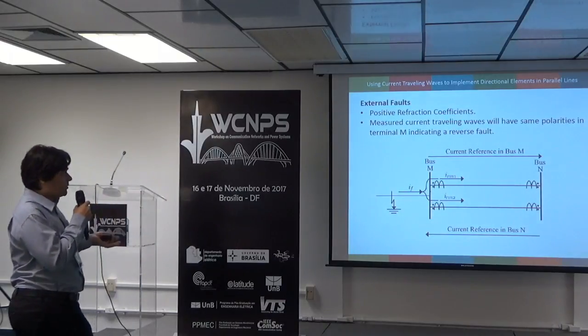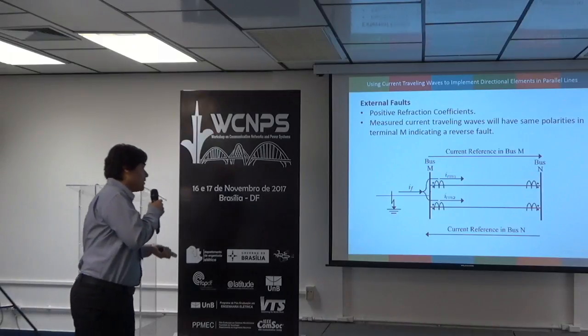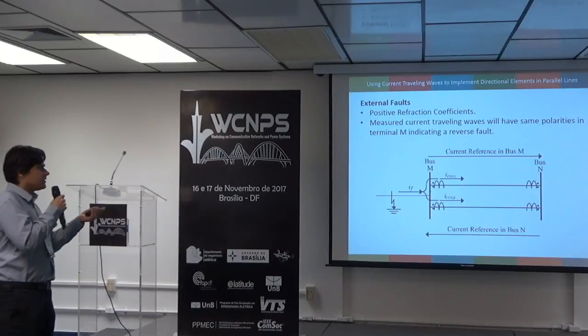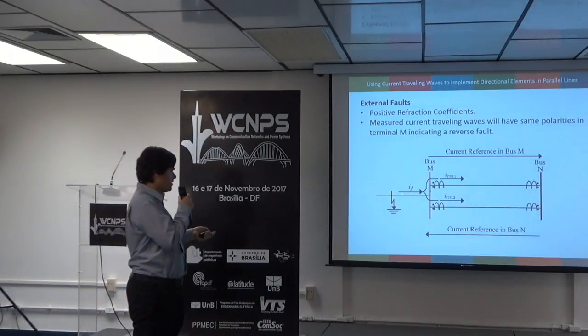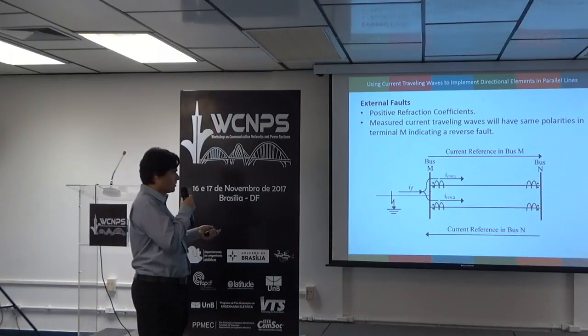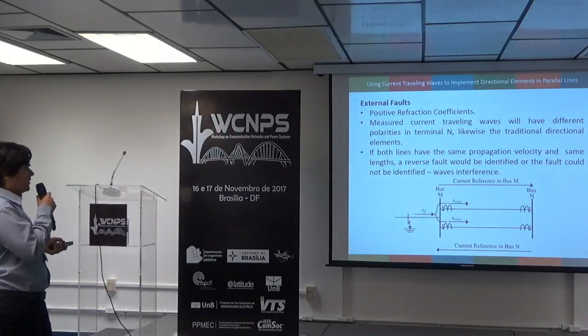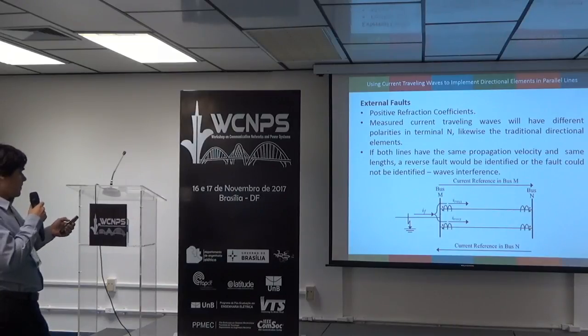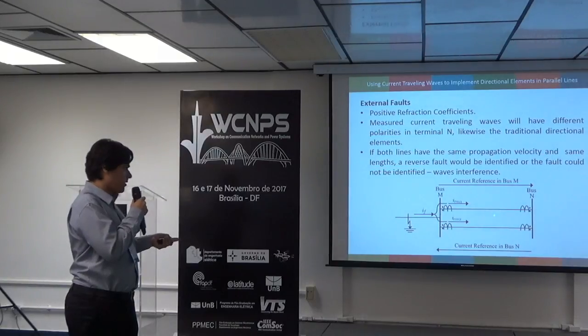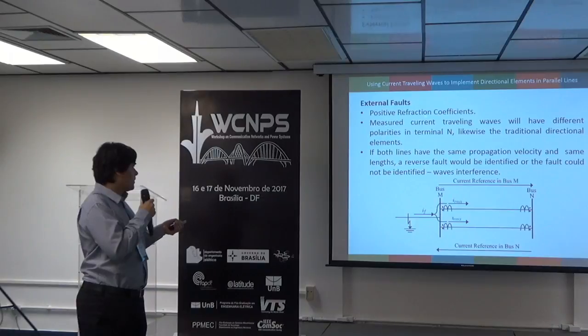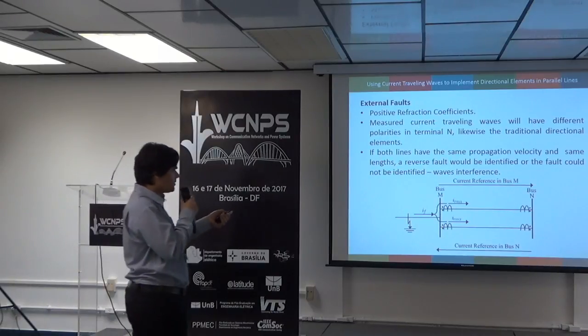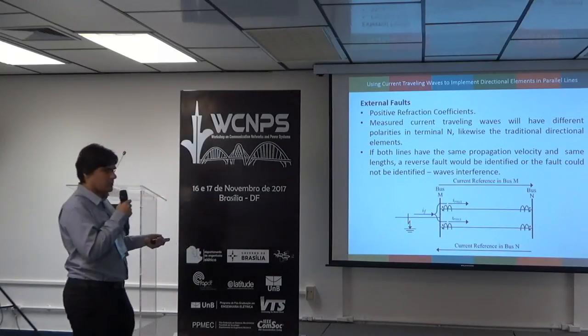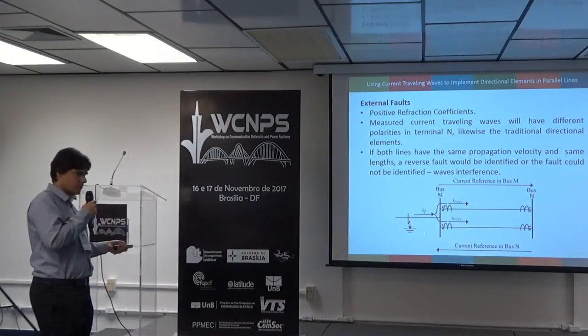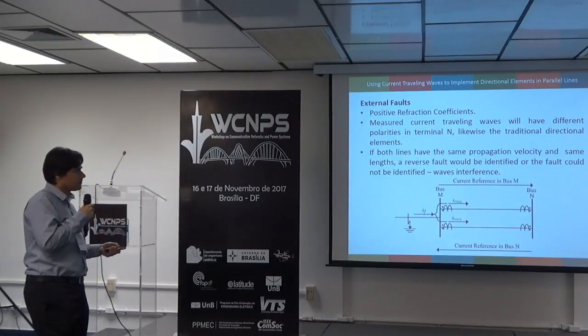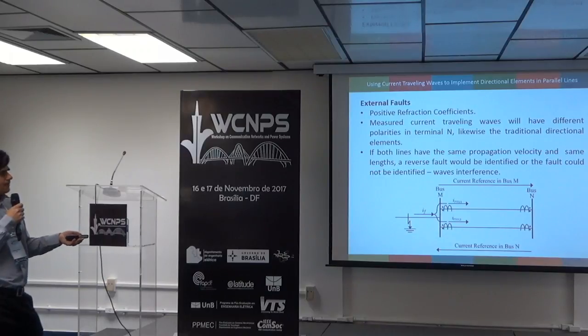External faults. Again, if you have positive refraction coefficients, the measured current traveling waves will have the same polarities in terminal M, indicating a reverse fault. This happens because the wave arrives at the bus and the refraction is seen at both current transformers of the parallel lines. But in bus N, if the waves do not arrive at the same time, the measured current traveling waves will have different polarities in terminal N, like traditional directional elements. Because in this case of an external fault, for bus M it will be a reverse fault. For bus N, it will be a forward fault. The traditional directional elements will identify it in this manner.